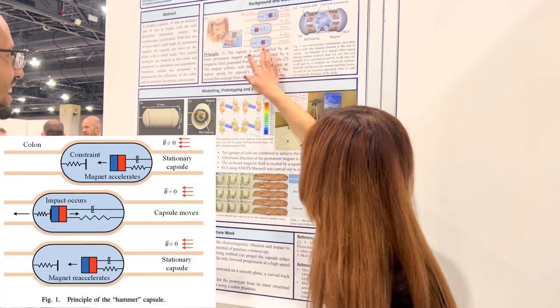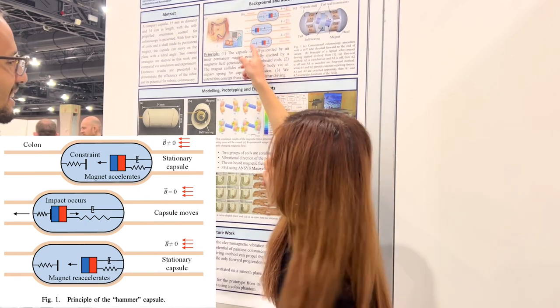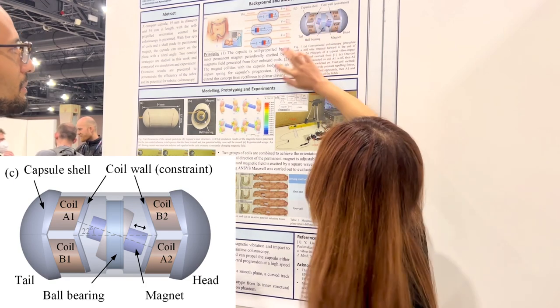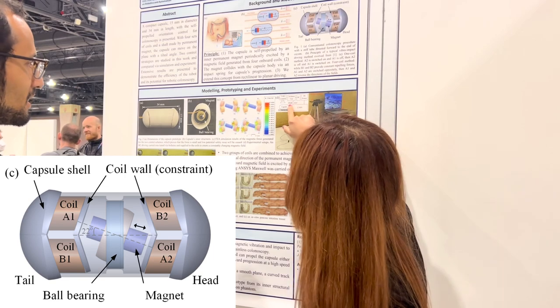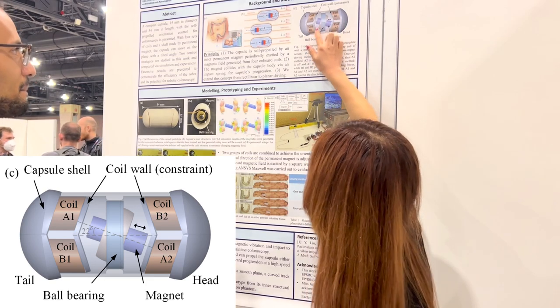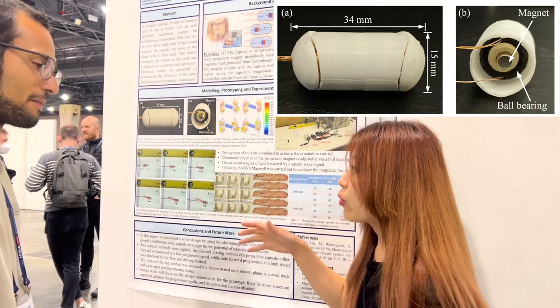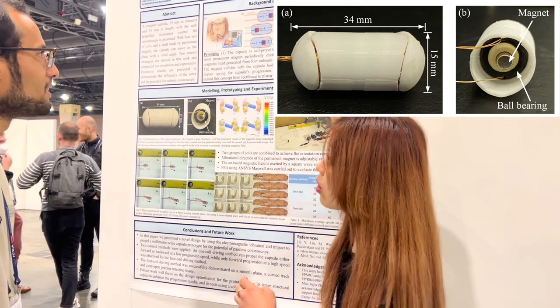So this is the purpose and this is the theory. When it's impacting inside, it can move the capsule forward. We actually use four coils inside the capsule. It forms two pairs: A1 and A2, and B1 and B2. When you excite A1 and A2 using the PWM signal, it's vibrating. And also you turn on B1 and B2, so there's a torque that pushes the capsule. The tether is sending a PWM signal, and also the power — both the control and the power are in the same wire to control the coil.